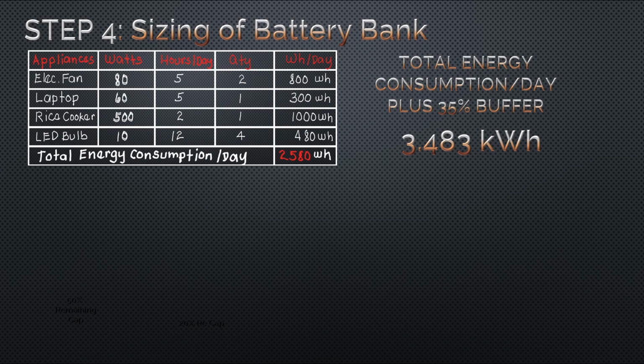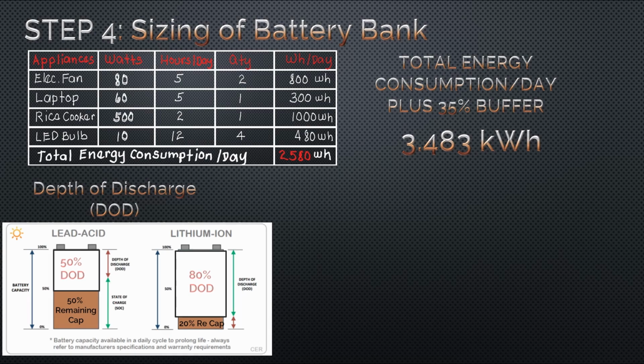The answer is no, because there is another parameter to be considered, and that is the DOD or depth of discharge of the battery. This parameter is recommended by the manufacturers of the battery, wherein the purpose is to lengthen the lifespan of the battery. Please note that the DOD for a lead-acid battery is different from the DOD of a lithium-ion battery. For instance, the lead-acid battery has 50% DOD, while the lithium-ion battery has 80% DOD. Maybe you will ask, how can we know if the battery has reached its percent DOD?